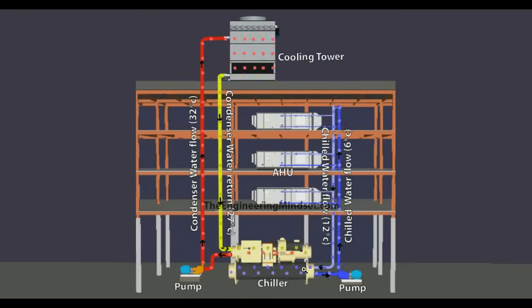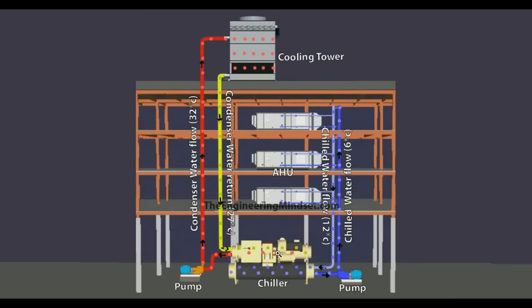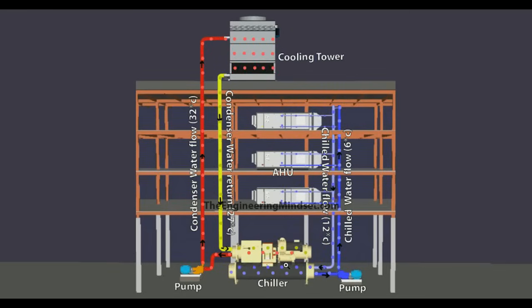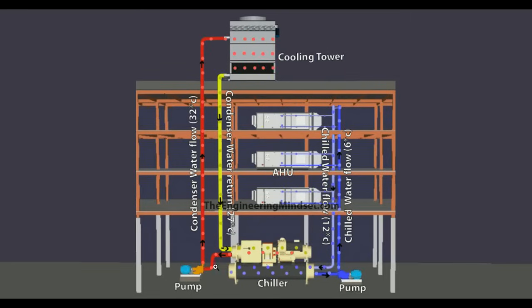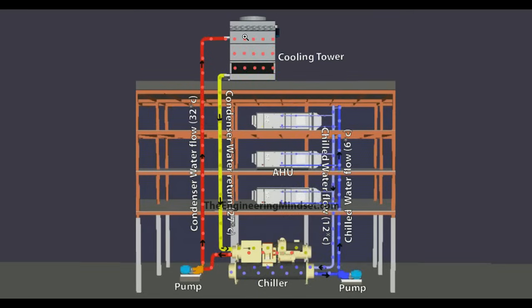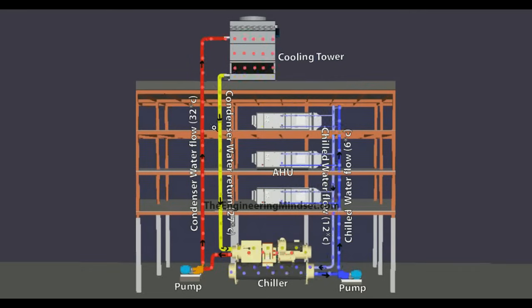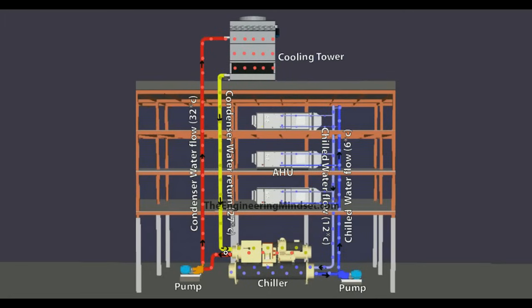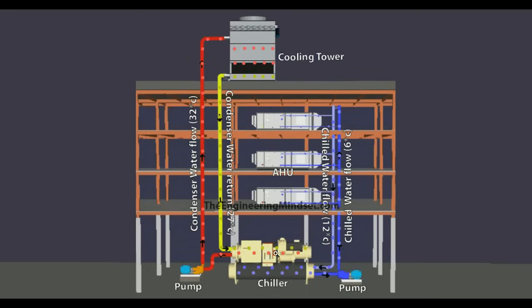This cycle repeats continuously. The heat that leaves this circuit is transferred via a refrigerant over to the condenser. These two systems are completely isolated from each other — there is just the refrigerant which transfers the heat between the two circuits. The heat picked up in the condenser is then pushed by another centrifugal pump up to the cooling tower, where air forced by a fan dissipates and rejects the heat from the building. This water is sent up at 32 degrees Celsius and comes back at 27 degrees Celsius, ready to pick up more heat.